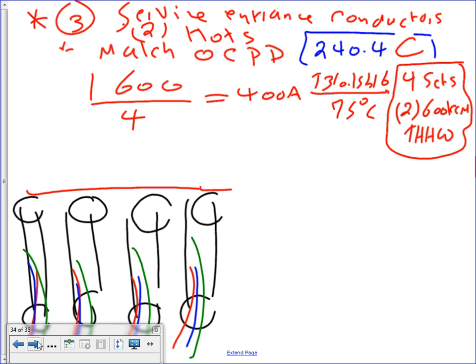Now we're going to go all the way to the neutral. Actually, I should have done it here. Oh, that's not a big deal. So, okay, you go to this step to size that neutral. Here's what we're going to do. Now we have 513 divided by 4. Adam, why did I divide by 4? Yes, 4 sets. Can I divide by 3 the neutral and the phases by 4? No. If you parallel the phases in 4 sets, what do you need to do in neutral? 4 sets. So how many runs you run the neutral depends on how many runs you run the phases. You can't just run 5 here and 2 here. No. Because every set has to have a neutral with it.